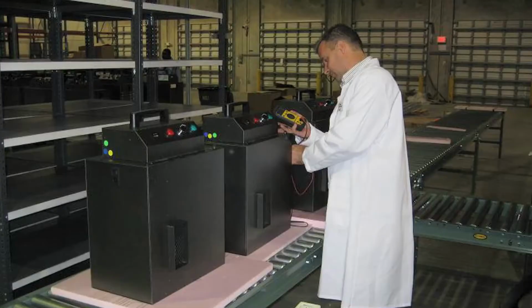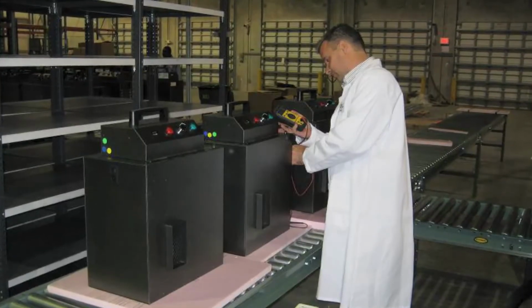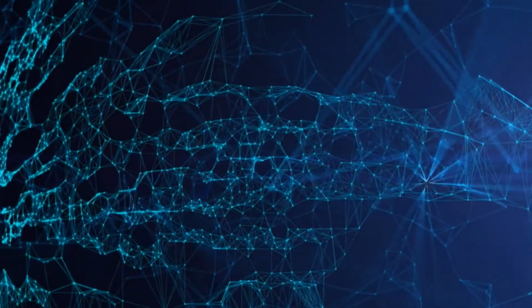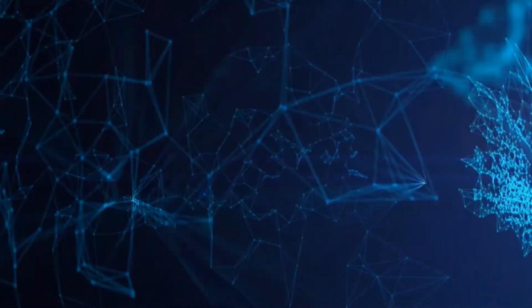In the marketplace, there's a variety of sensors. Most of them are electrochemical sensors that are used to measure a variety of gases, both inert and corrosive. These devices were never designed to measure potent oxidizers with electrochemical potentials over 1 electron volt selectively. So when they respond to oxidizers, they respond to them as a group. So they'll routinely register positive for not only hydroxyls and ozone together, but hydrogen peroxide and hypochlorites, bleach, and lemon juice, and other common oxidizers. It's not to criticize them as devices, it's just that they are being inappropriately used in trying to selectively measure either ozone or hydroxyls.